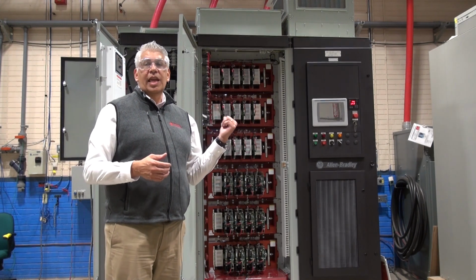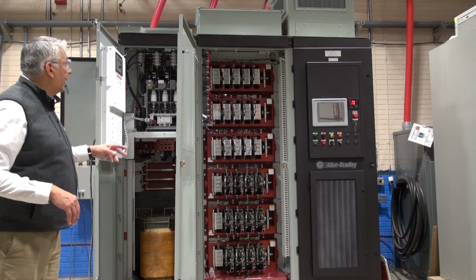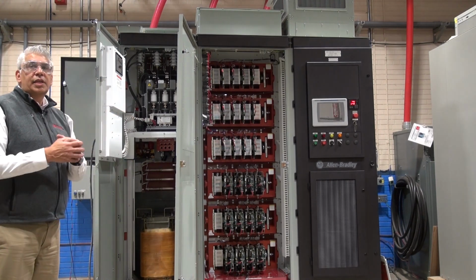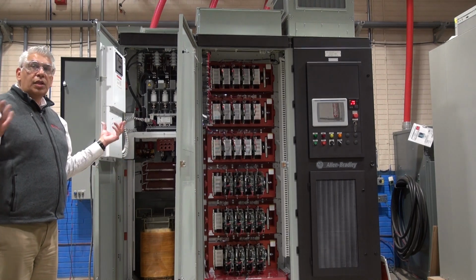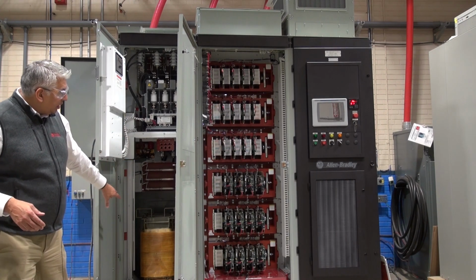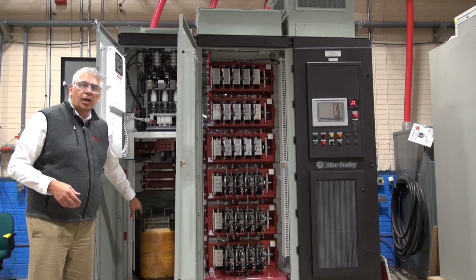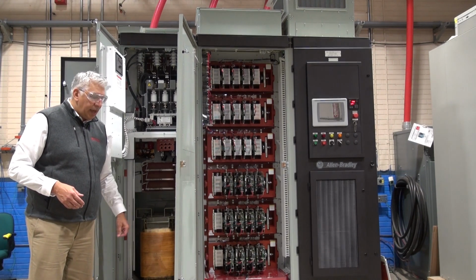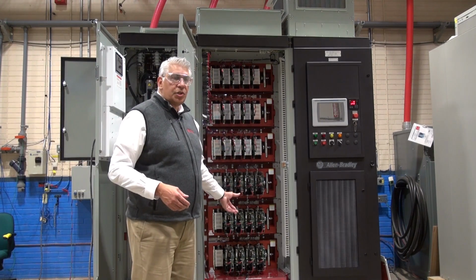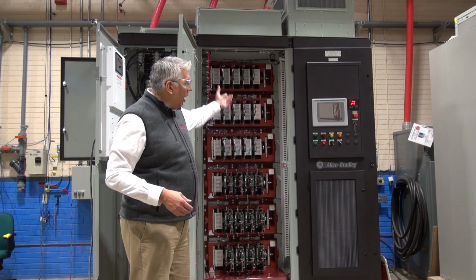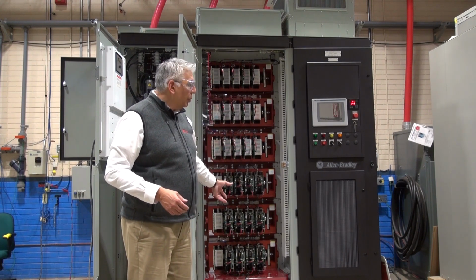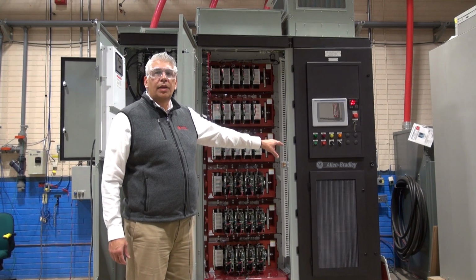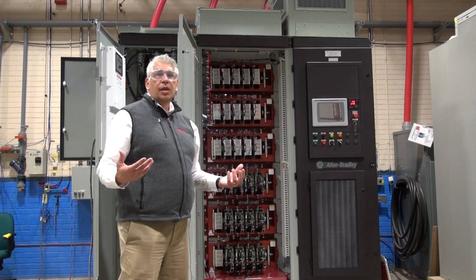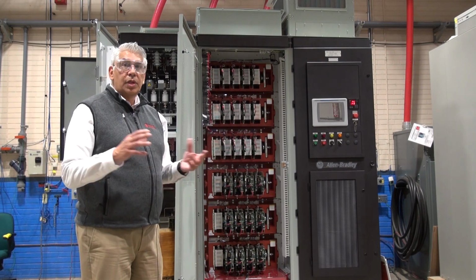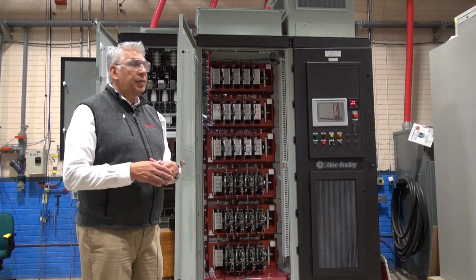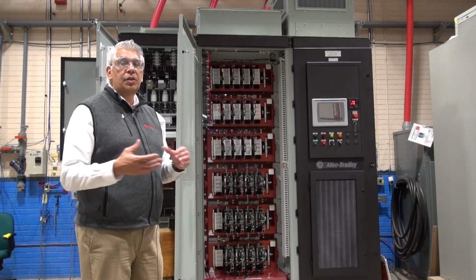So this configuration is an A-frame, direct to drive. It has an integral transformer as an option, but the nice thing is then you've got your branch circuit and disconnect all in one package. Instead of the isolation transformer, you've got a very small line reactor in the bottom of this cabinet. Essentially, the center section is the inverter along the top 3 modules, the rectifier along the bottom 3 modules, and then in the far cabinet we've got a common mode choke that allows you to operate standard motors. You don't need a special inverter duty rated motor because of the common mode choke. Again, 3 cables in, 3 cables out.